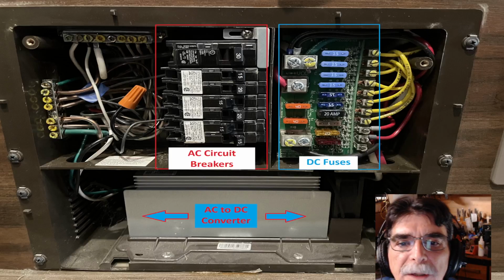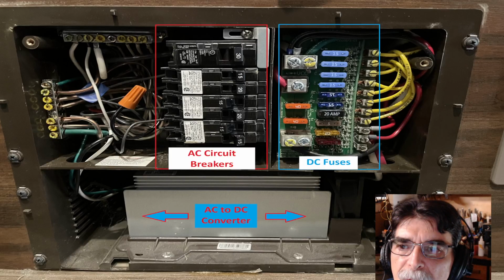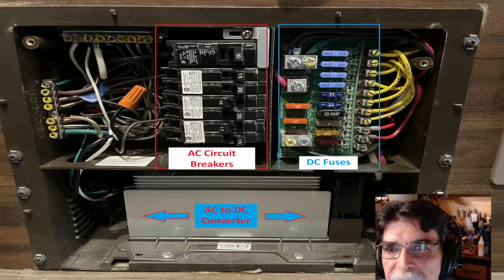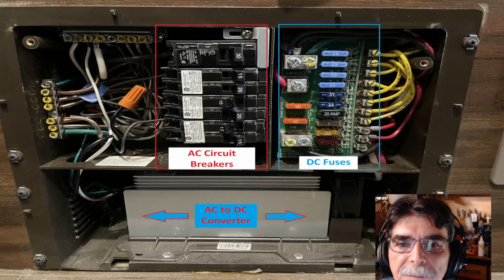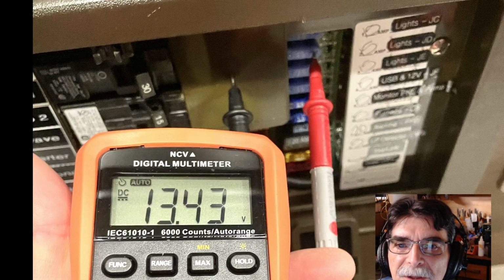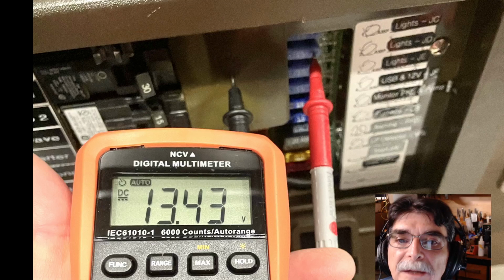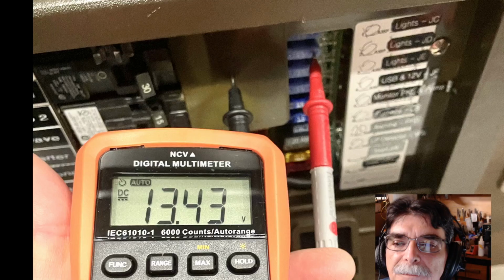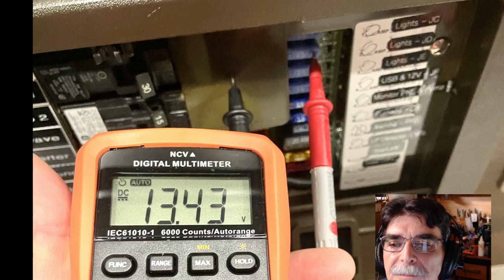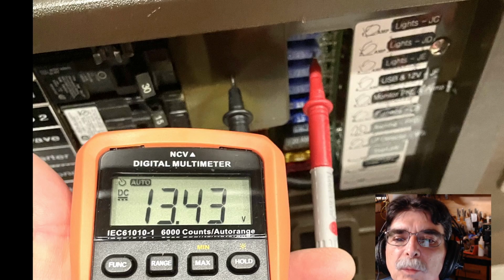Remember a few slides back I showed you the voltage at the battery, measuring under the step. Here I'm measuring the battery again, right at the panel with the cover on. Before, the battery voltage under the step was 13.5, and here it's 13.43. You'll notice the red probe is touching a fuse and the black probe just goes into the plastic.